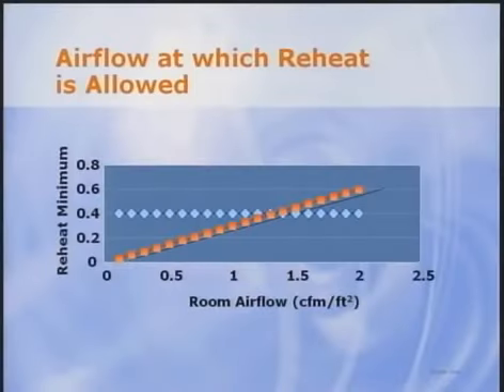A lot of people seem to gravitate to setting the reheat minimum at 30% of its design airflow. While it's simple, this could cause some issues with respect to heating and stratification. Steve will cover that in a few minutes. It's interesting to note that until the space design airflow reaches 1.33 CFM per square foot, the 0.4 reheat minimum allows a higher airflow to be reheated. Okay, let's cover the last two exceptions.